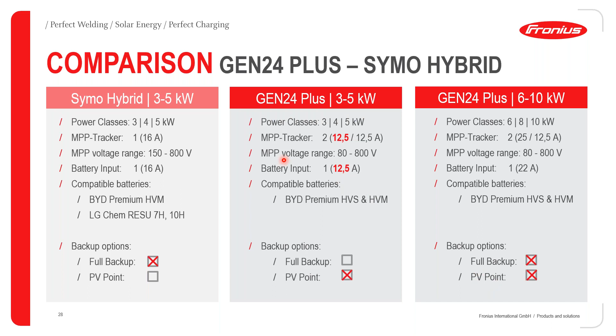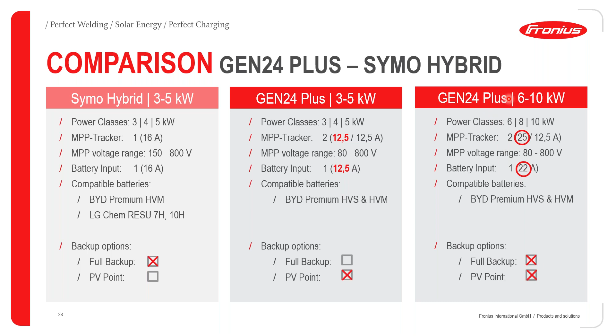Backup options include the full backup and, of course, the PV point. I'll be shedding more light on these 2 features after I have compared it with the other power classes of the Gen 24 Plus SYMO. So for power classes 3 to 5 kilowatts, to be specific 3, 4, and 5 kilowatts, the MPP tracker current ampacity is equal in this case, that is 12.5 each. And then the MPPT voltage range is the same as the 6 to 10 kilowatt power classes, but the battery input ampacity is 12.5 amps as against 22 amps for the power class 6 to 10, and then 25 amps in terms of MPPT1 for the 6 to 10 kilowatt class when compared with that of the power class 3 to 5 kilowatts, as you can see. Good. And then another difference is that it doesn't offer the full backup option as is offered by the power class 6 to 10 kilowatts.